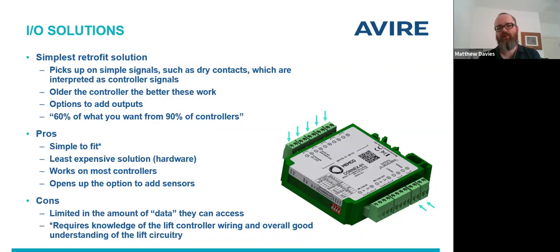That opens up options to add sensors, which I'll talk about more on the next slide. The downside is you have a limited amount of data you can access. That unit has 5 inputs, so it can monitor 5 different things. If you're looking for every single fault code out of a controller, you'd have to put in a lot of these units and do a lot of wiring.